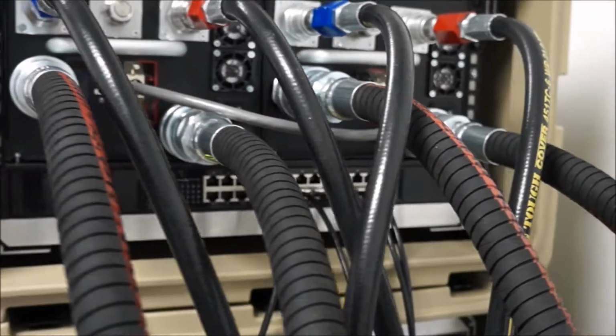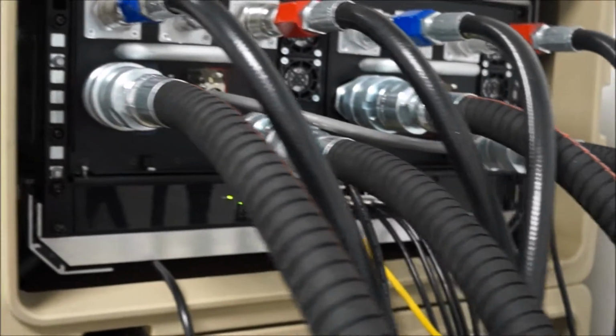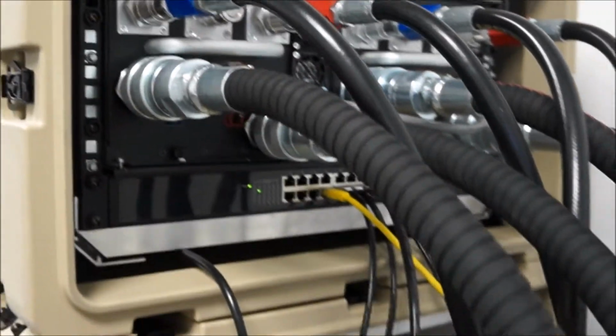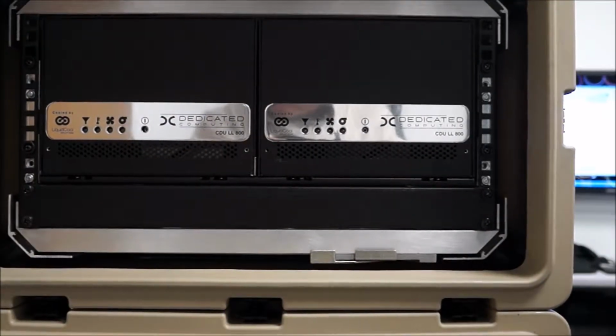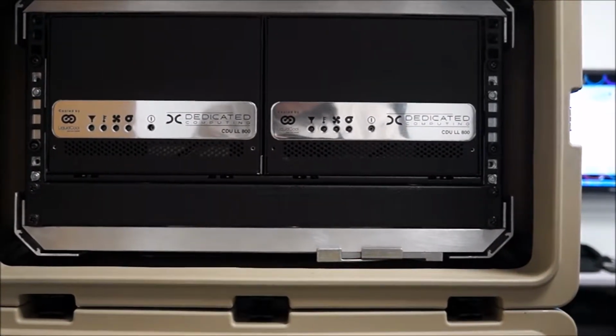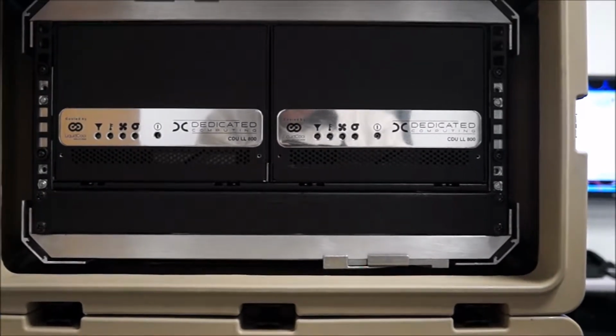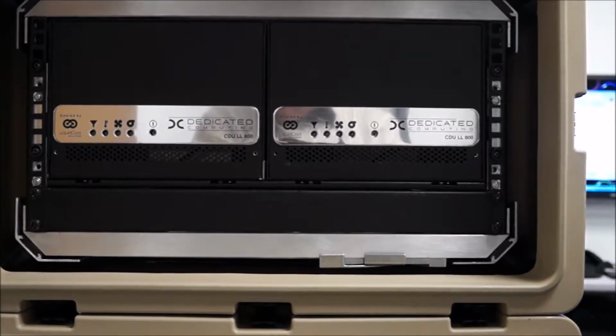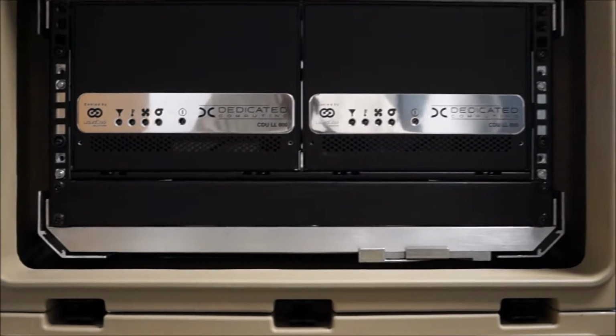In this redundant configuration, only one of the CDUs is operating at any time. If the primary CDU fails, the second CDU starts operating automatically with no loss of cooling. These CDUs are also equipped with an RJ45 port for remote monitoring via a web interface.